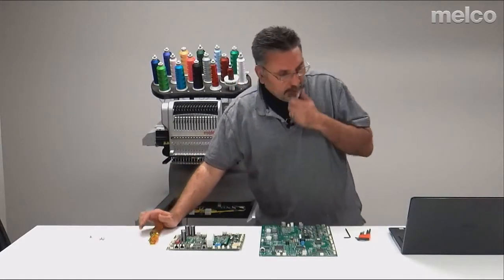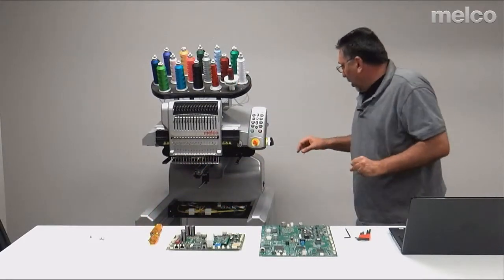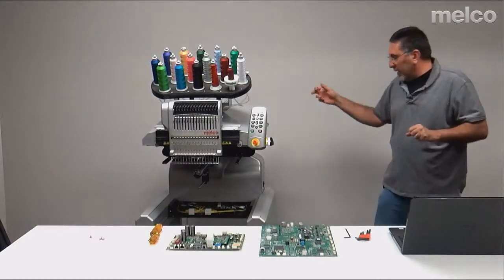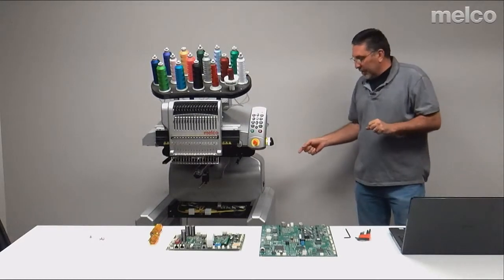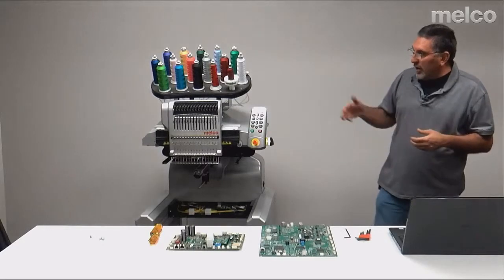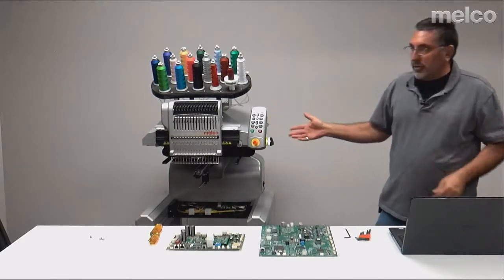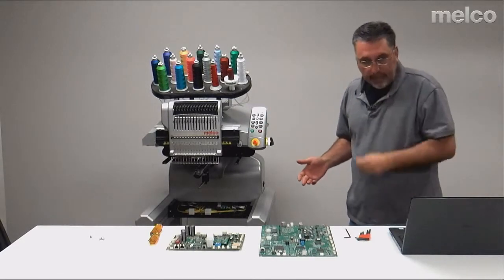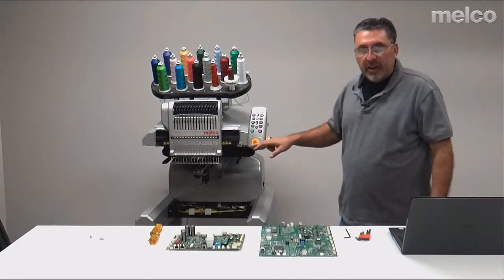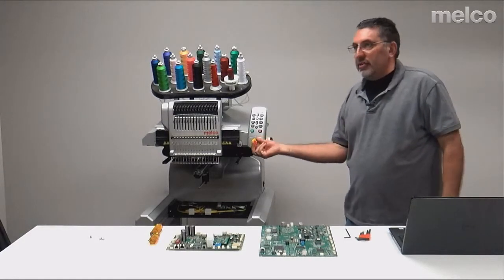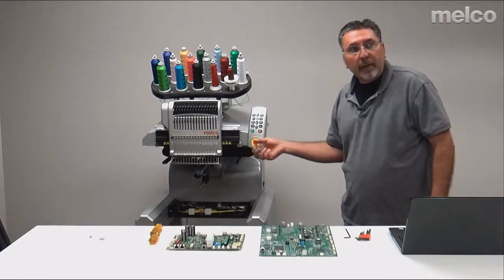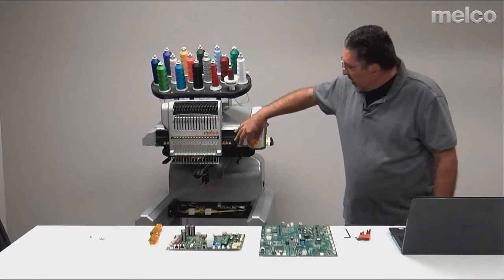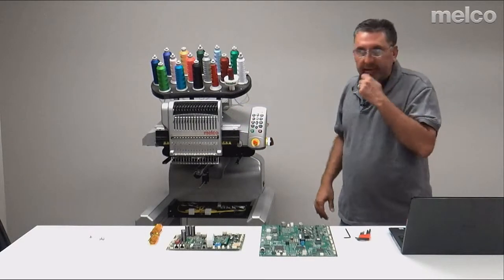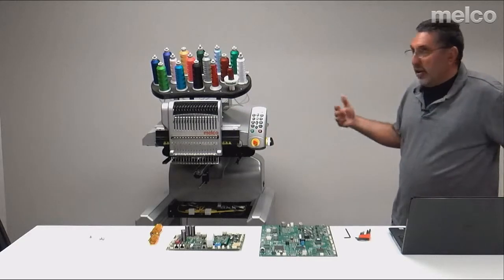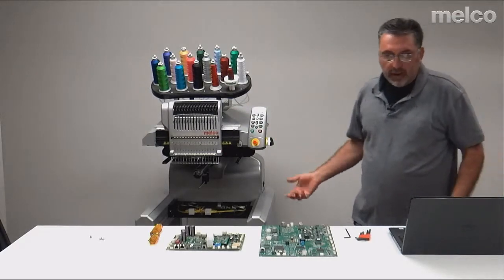Thank you. Yep. So our Ethernet connections hook back up, our power cords hook back up. We are now ready to power this machine back on again. First thing you're going to want to check is it's very easy to accidentally push in the emergency stop. So twist that emergency stop button to the right just to make sure that you didn't hit it when you were in there working.